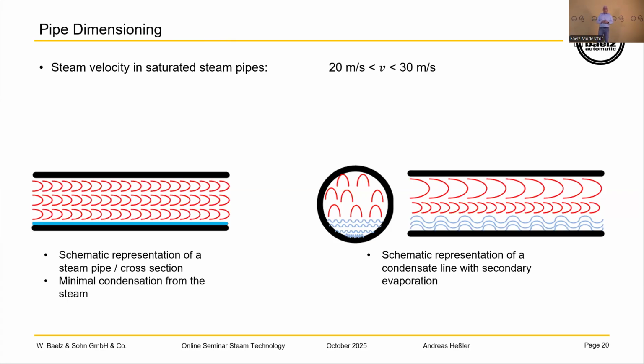Velocities in the steam pipe: what we normally prefer for saturated steam, because in saturated steam there could be some water droplets, would be between 20 and 30 meters per second. And if you go much lower on the saturated steam velocity, you have more condensate because you are so slow with the speed. So it would be good to have them between 20 and 30 meters per second. So try to have this velocity.